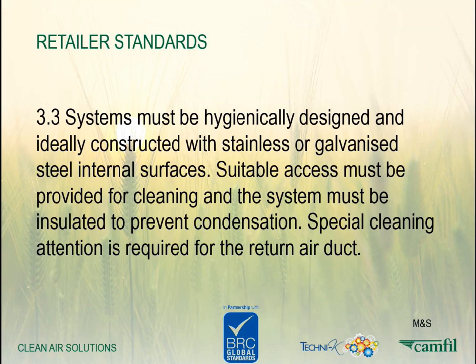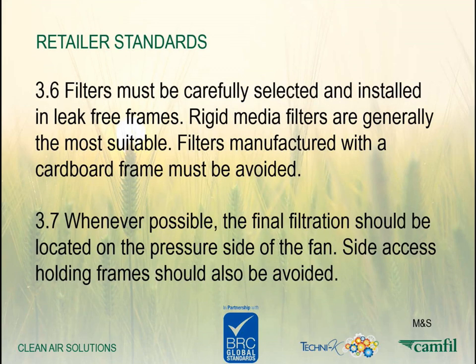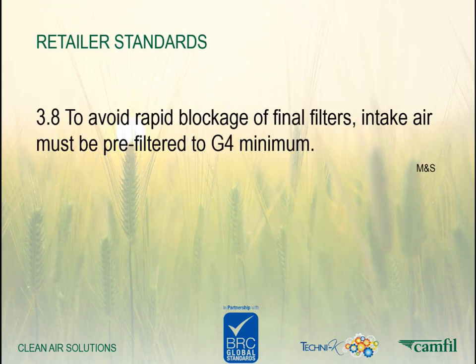The third section talks about the fact that we need a hygienic design and access, and that reiterates the fact that we need to maintain and keep the system clean. Here, M&S are saying that when we know what filter we're going to put in, we need to make sure that it's installed correctly to make sure it doesn't leak. They also go on to specify where exactly the filter should be. And then they say what the pre-filter should be as a minimum. So here they say G4, but they don't actually say what the final filter should be.